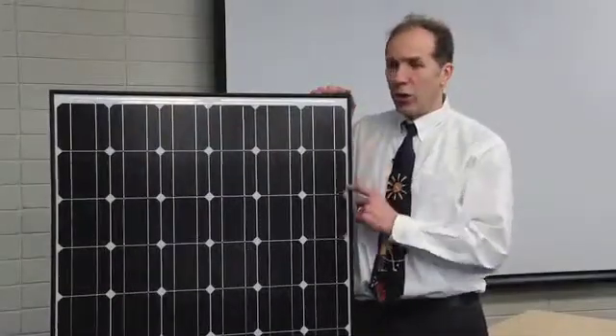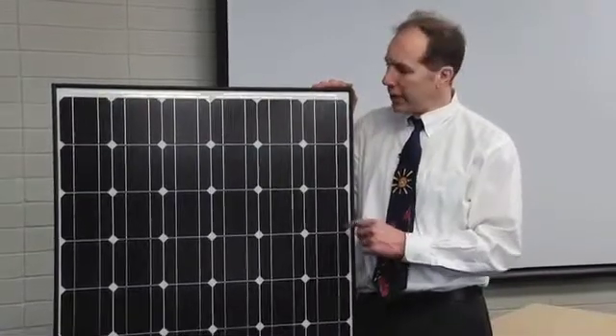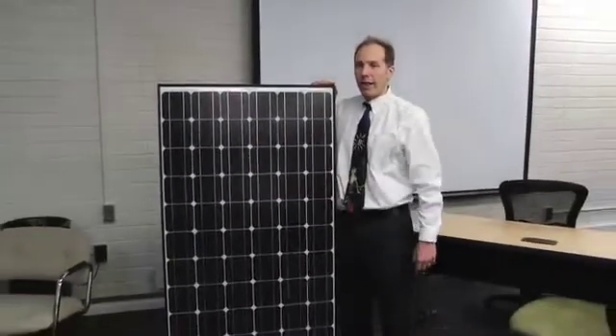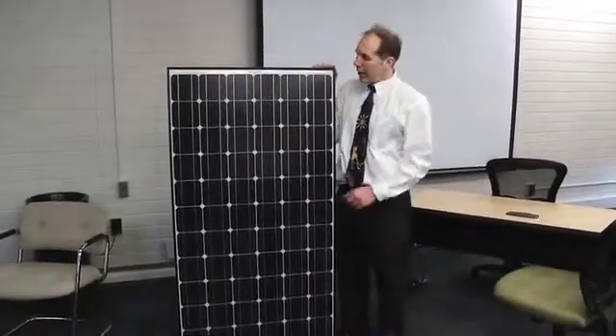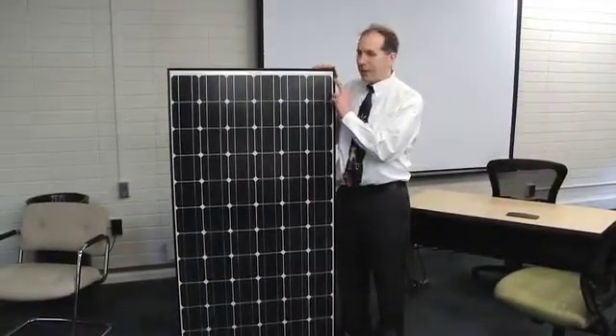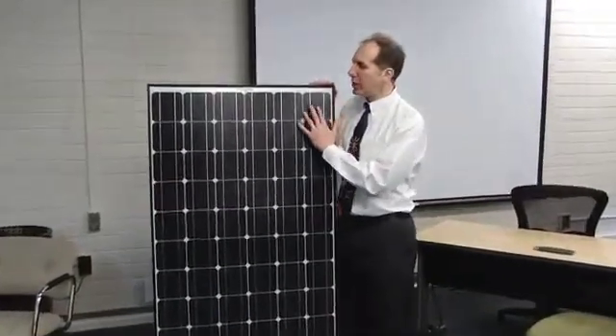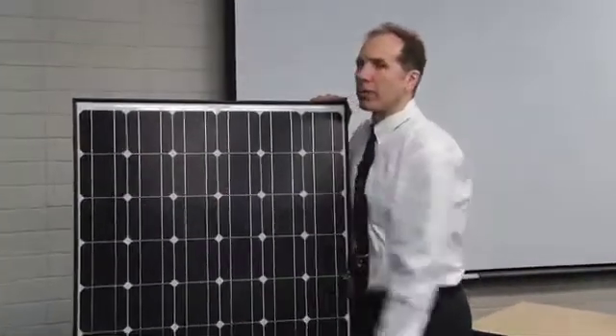The 72 solar cells in this module are wired in series, top to bottom, top to bottom, top to bottom, all around the module. There are bypass diodes. I believe that this module has three bypass diodes, one for each pair of two columns of solar cells.